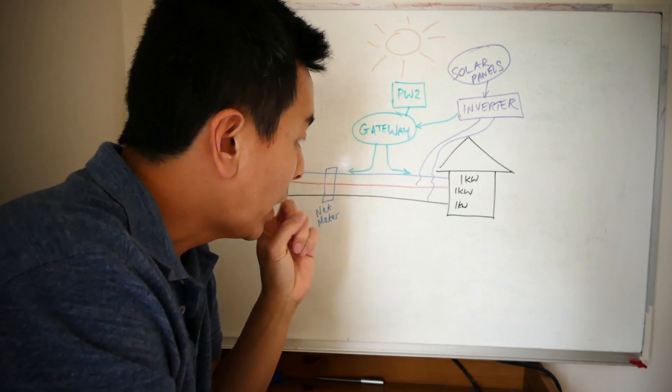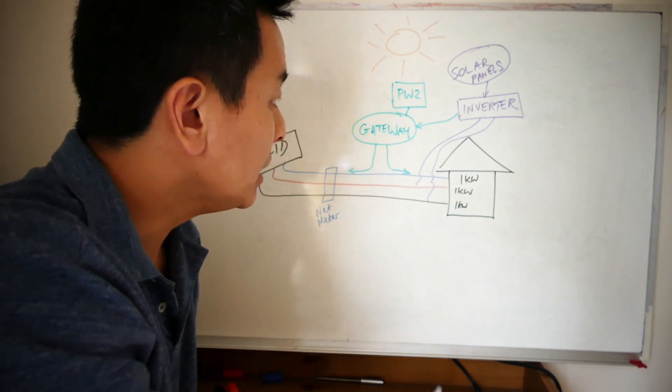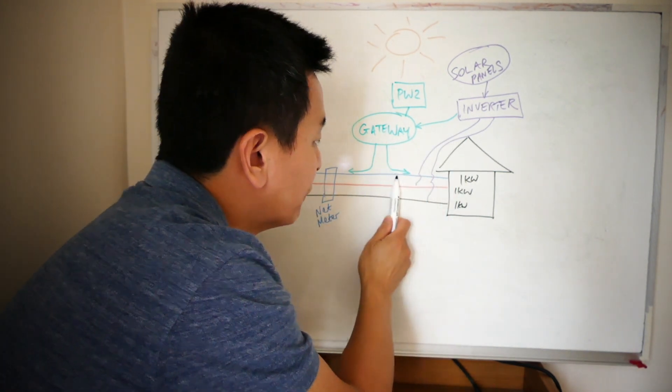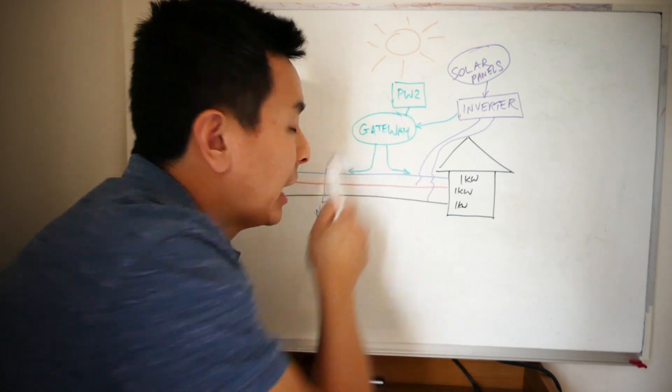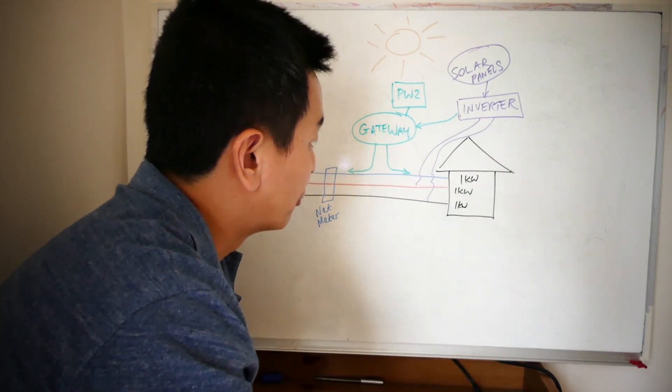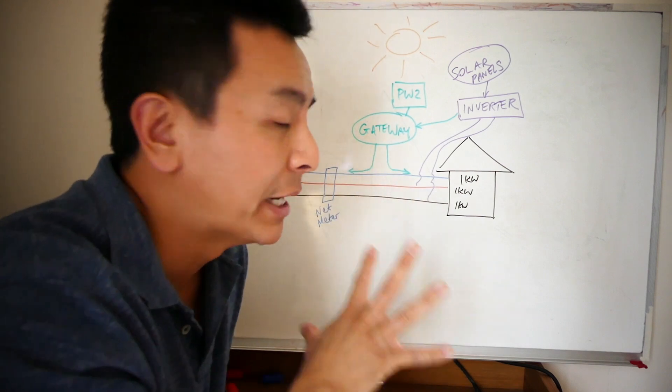What happens in that situation if you've got a blackout? Okay, so in a blackout, the gateway will have enough charge to power your home on this phase alone until the Powerwall 2 drains itself to zero. Because it's a three-phase inverter, you need three phases of power from the grid, right, or from some sort of battery source.